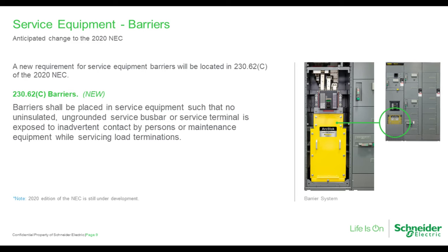So on this slide, we all know that the current NEC is the 2017 edition. In it, you will find installation requirements related to barriers and certain types of gear. And specifically in 408.3, you'll find requirements for barriers in service panelboards and switchboards and switchgear. But did you know that that requirement will be expanding in the next edition of the NEC? So the 2020 NEC, which will be available about 1 month from today, will have a new requirement.